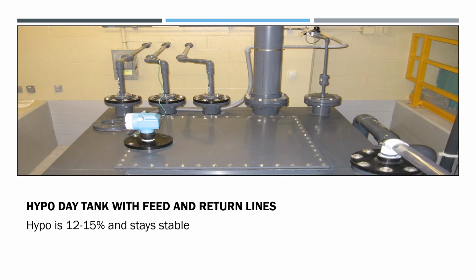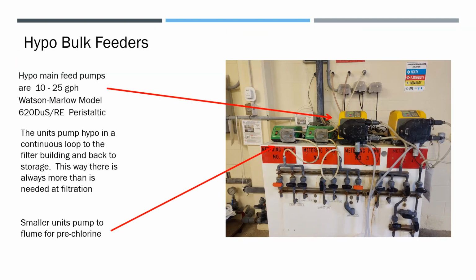This is a picture of the hypo day tank and the feed lines with the return lines. Again, the hypo that they use is generally between 12 and 15%. It stays pretty stable in this arrangement. These are the main hypo bulk feeders on the west side by the day tank. The main feed pumps are 10 to 25 gallon per hour Watson-Marlow model 620 DUSRE peristaltic pumps. They feed a quantity of hypochlorite through the continuous loop.